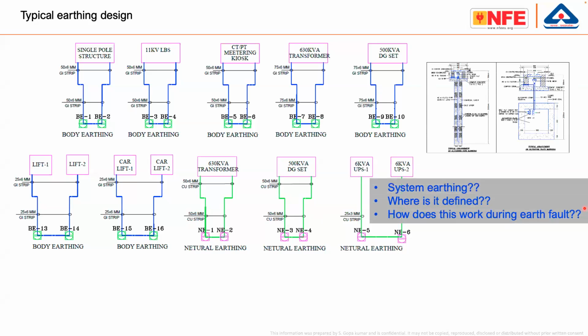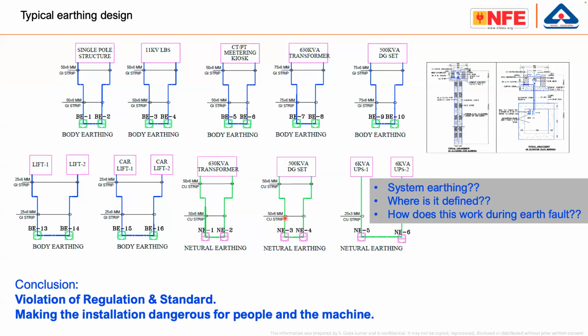But if we try to understand this diagram and what is practically going on, the first question is, what kind of system earthing is it? Is it TT or TN-C or TN-S, or what kind of system? Actually, what we are following is an undefined system. Maybe we have to do research and find out what kind of system earthing it is and how to achieve fault protection in this particular case. So whatever you are seeing in the picture, separate for neutral, separate for body, separate for lift, separate for UPS, this is an absolute mistake. It is a violation of regulations and standards, and it makes the installation highly dangerous for people and machines. Unfortunately, I would say the majority of installations in India are of this type.